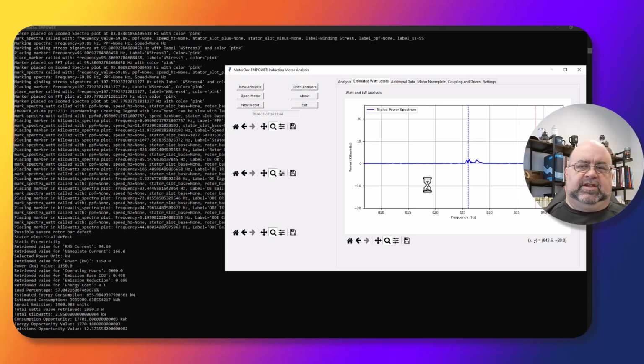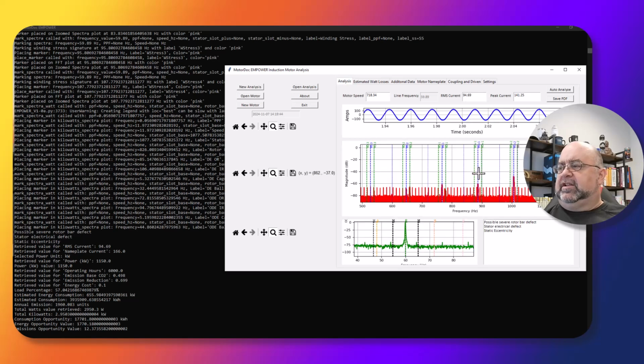So looking at this, that tells me my final analysis was right. Definitely not a rotor bar issue, but definitely some stator electrical and static eccentricity, meaning I've got some electrical issues going on and I have eccentricity. Now, it did not find the winding stress signature, that didn't pop up, but that's about it. No bearing issues at this point, although it does look like I'm closing in on some lubrication stuff due to the volume. And when I get 3 digits worth of watts in a bearing, it's definitely going to be an issue.